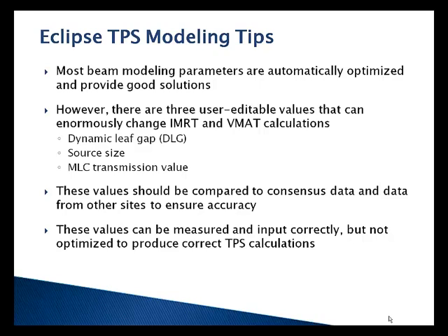Those numbers, one, you can physically measure them, but every once in a while, for things like the HD120 MLC, you'll physically measure a leaf gap of, say, 0.3 millimeters, which is probably the correct measured answer. But the system's model actually works better with a value of around 0.8 millimeters. And the difference between that can be 3 or 4%. So we don't even have to just measure these correctly. We have to make sure that our final dose calculations are correct.